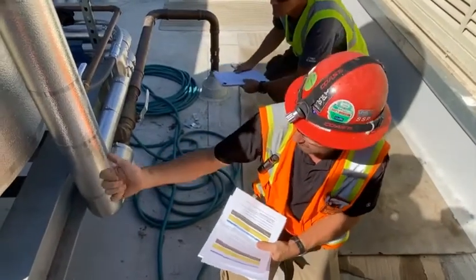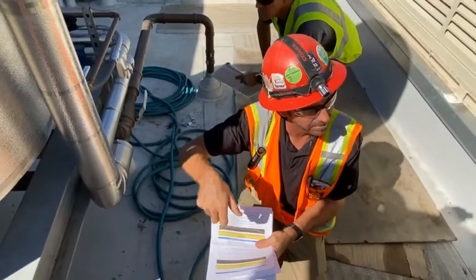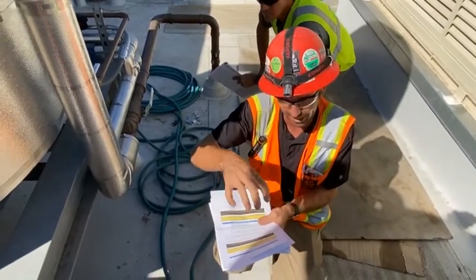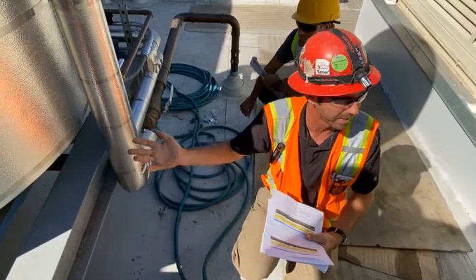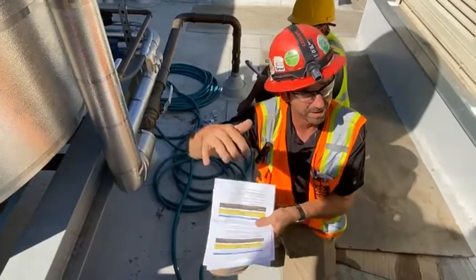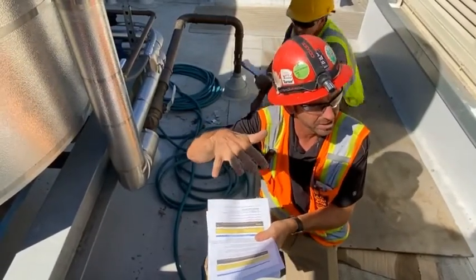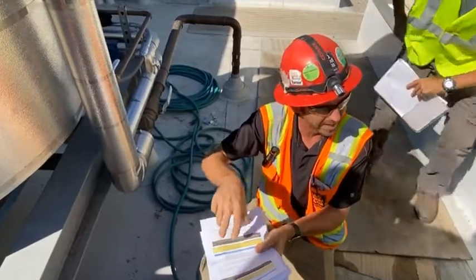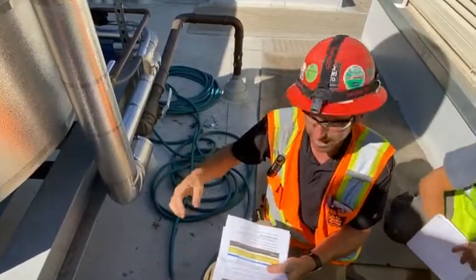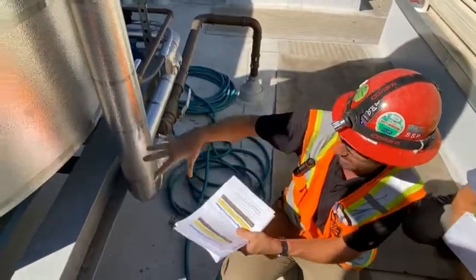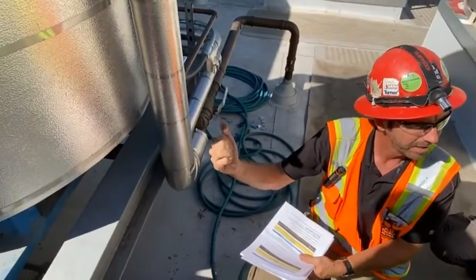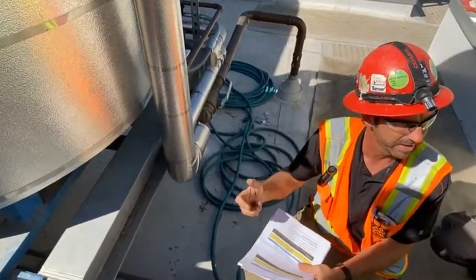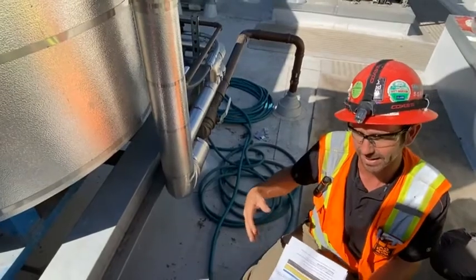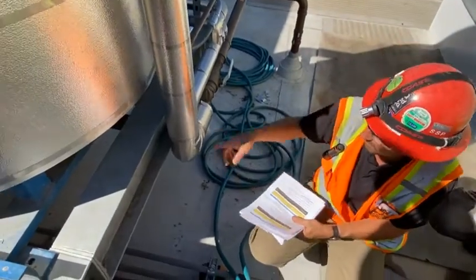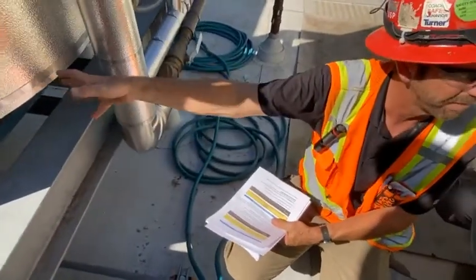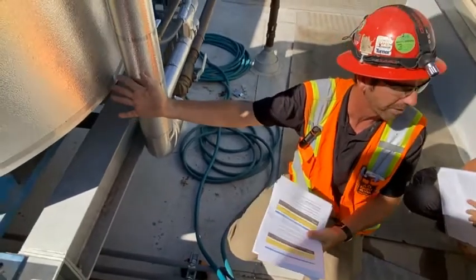If you put a reducer right in the valve and you open it and the debris is enough that it can build up when you try to shut the valve, you'll have a problem, okay? You won't be able to shut the valve back off. That's why I recommend putting at least like a 12-inch nipple, and then you can put like a 90 and then reduce after that, okay? Because if you do your blow down and it builds up that 90 and you shut the valve and it won't drain out, at least you can unthread that and then clean out that fitting, okay? Does that make sense? On a tank like this, it has a bigger valve than like a normal 3/4 garden hose size, okay?